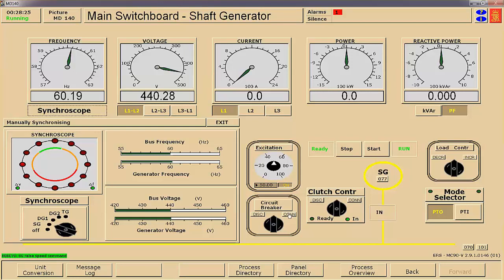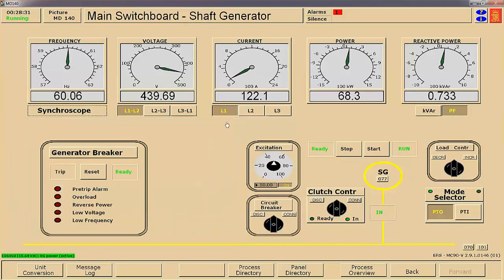So basically what you're doing is increasing the speed and the voltage slightly higher so that it automatically picks up some load. So I'm off. Let's exit. Now I'm going to transfer all of number 1 to the shaft generator. So I'll leave it the way it is. Actually, I'm already above 60, so I'm going to decrease number 1, which will transfer load over to the shaft generator. Now I'm just going to increase and decrease, same exact way.